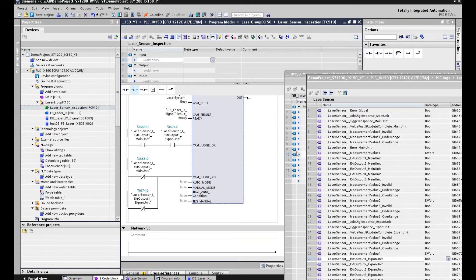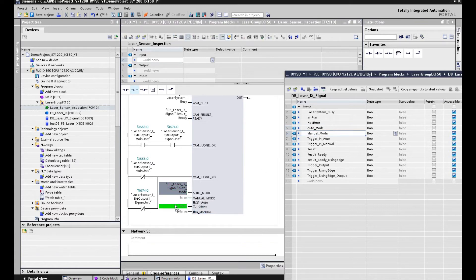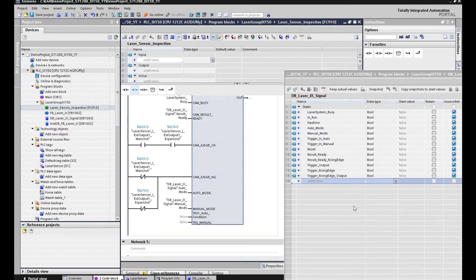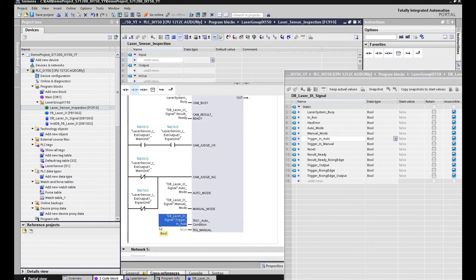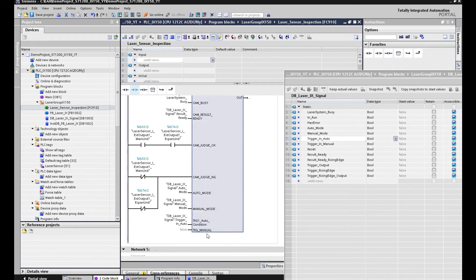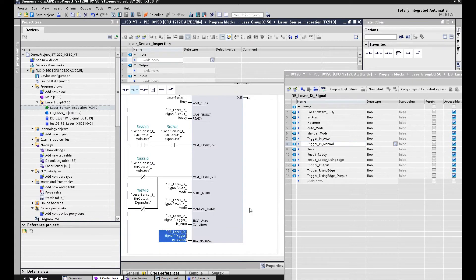And lastly, auto mode and manual mode — we can drag the auto mode here and drag the manual mode here. The trigger auto condition, we can use trigger in auto. This trigger in auto tag is controlled by your automatic logic — for example, if your sequence gets to step 7 or step 10, at that step you trigger. Or at step 10, your cylinders need to be at a certain position, and once your cylinders are in position, you go to trigger. So trigger in auto can be controlled by some logic. Next, that is the trigger in manual — we grab this tag here.